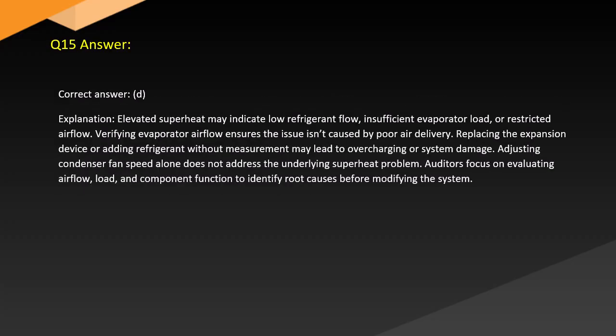Answer. Correct answer, D. Explanation. Elevated superheat may indicate low refrigerant flow, insufficient evaporator load, or restricted airflow. Verifying evaporator airflow ensures the issue isn't caused by poor air delivery. Replacing the expansion device or adding refrigerant without measurement may lead to overcharging or system damage. Adjusting condenser fan speed alone does not address the underlying superheat problem. Auditors focus on evaluating airflow, load, and component function to identify root causes before modifying the system.